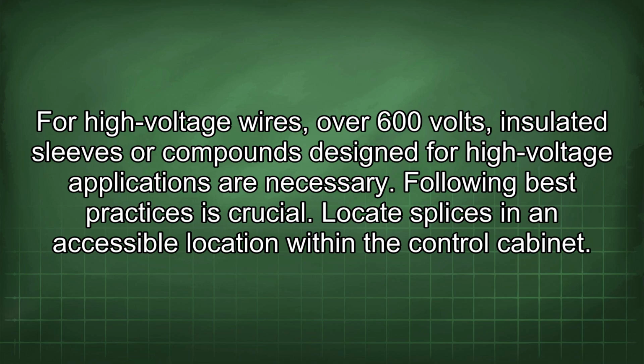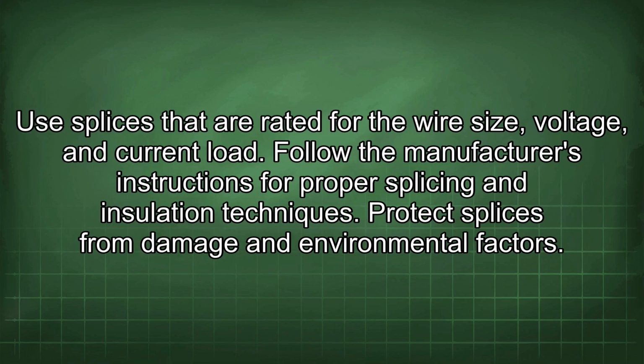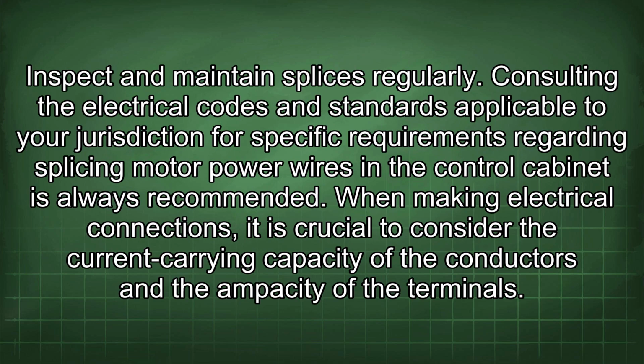Following best practices is crucial. Locate splices in an accessible location within the control cabinet. Use splices that are rated for the wire size, voltage, and current load. Follow the manufacturer's instructions for proper splicing and insulation techniques. Protect splices from damage and environmental factors. Inspect and maintain splices regularly. Consulting the electrical codes and standards applicable to your jurisdiction for specific requirements regarding splicing motor power wires in the control cabinet is always recommended.